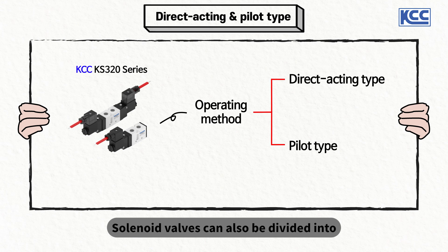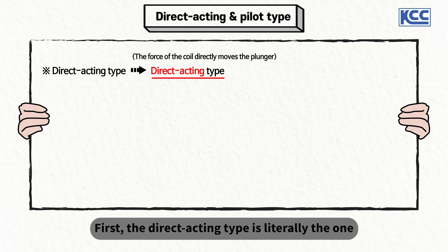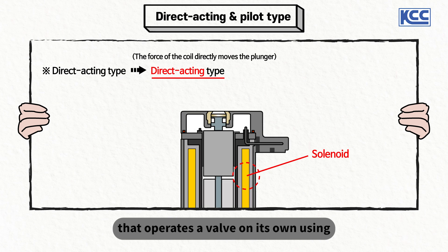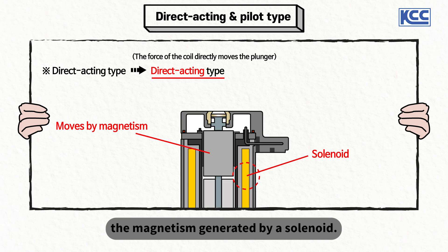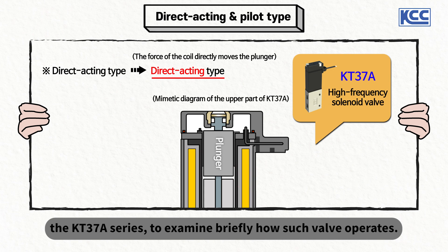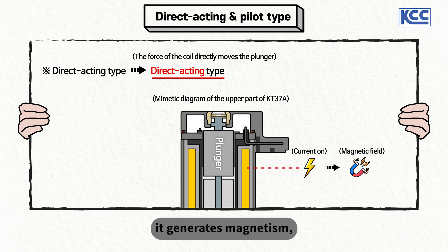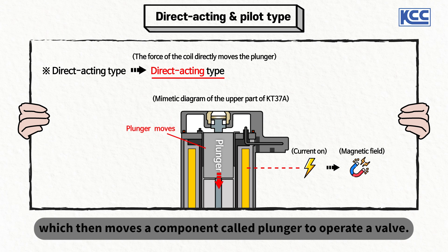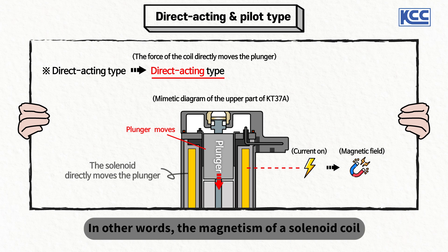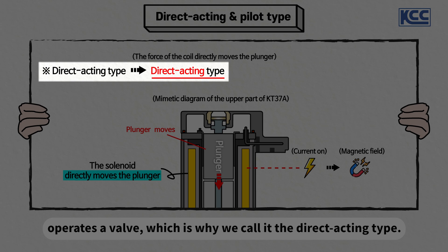Solenoid valves can also be divided into direct acting type or pilot type, depending on how the valves operate. The direct acting type is literally the one that operates a valve on its own using the magnetism generated by a solenoid. Looking at KCC's direct acting valve, the KT37A series: once current is applied to a solenoid coil, it generates magnetism, which then moves a component called a plunger to operate the valve. The magnetism of a solenoid coil directly activates a plunger and subsequently operates the valve, which is why we call it a direct acting type.